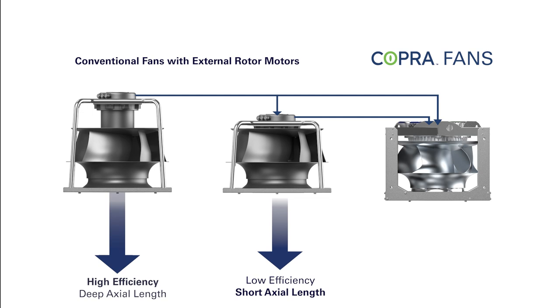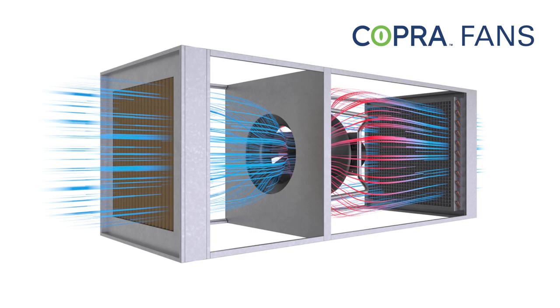For systems with the motor inside the impeller, the fan is shorter. However, the internal motor causes unavoidable turbulence in the impeller, considerably reducing efficiency. With Copra fans, we put an end to compromises. The Copra fan's short motor design does not protrude into the impeller and does not generate any turbulence. The result is a perfectly paired impeller and motor, combining the best efficiency with the shortest axial length.